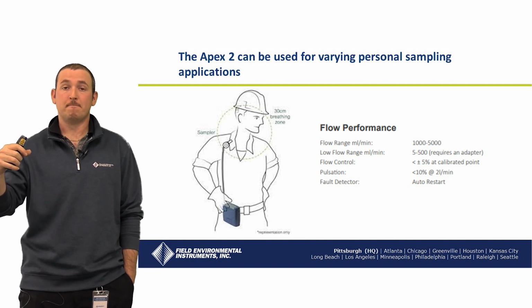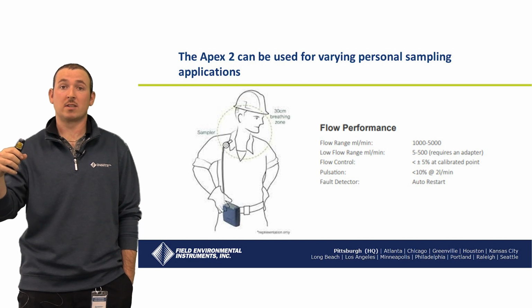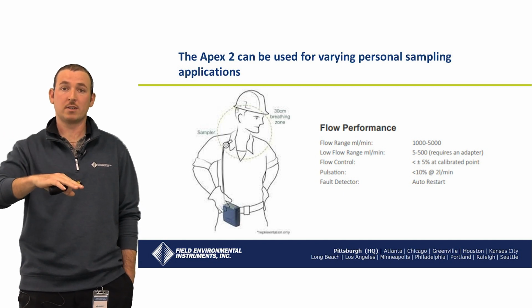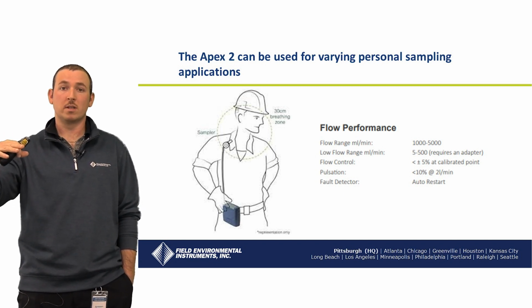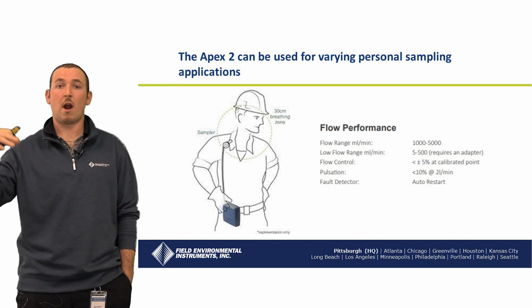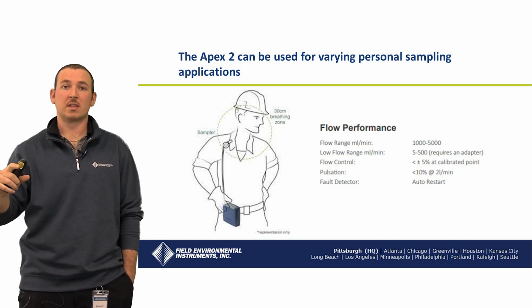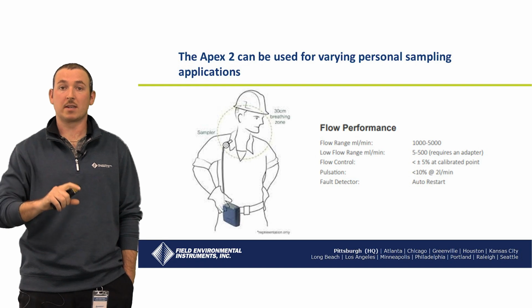And that's typically at plus or minus 5% of your calibration point, just because the pump will oscillate as it's running. One thing to note though is the Apex 2 can get down to those lower ranges, the 5 to 500 milliliters per minute range, but that does require an adapter, which is just something that you would run in line between the Apex 2 and your filter.